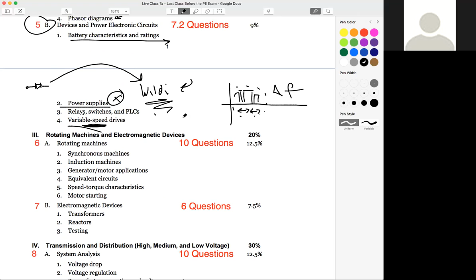Volts per hertz are great on variable speed drives, and the newer ones even come with a volts per hertz control. But the important thing to know is that your output from your VFD is not a true AC. It mimics AC by sending pulses of different amplitudes and different wavelengths—these individual wavelengths here. So by doing that, you're actually changing your frequency, your delta. And of course, if you don't change your volts along with it, it can have a negative effect on magnetic fields for reactive components.